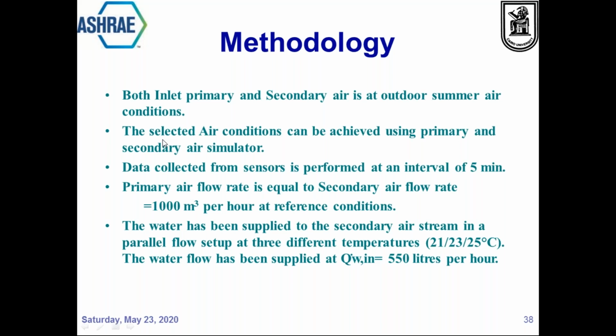The water is supplied to the secondary airstream in a parallel flow setup at 3 different temperatures. Why? We thought the temperature of the water to be sprayed will be near the wet bulb temperature, which will vary. So we took it at 21 degrees centigrade, 23 degrees centigrade, and 25 degrees. We went even further, and we thought sometimes, maybe if you have a chiller plant nearby, and we have some excess chill water, we can try at 12 degrees centigrade to use some of the water. So the water flow rate provided was 550 liters per hour.